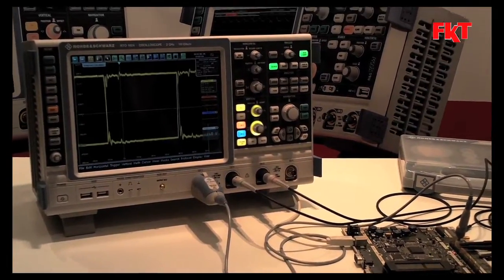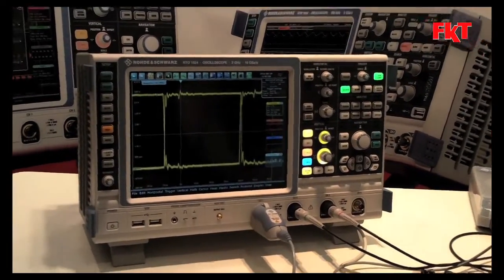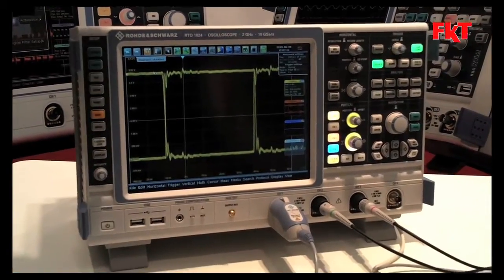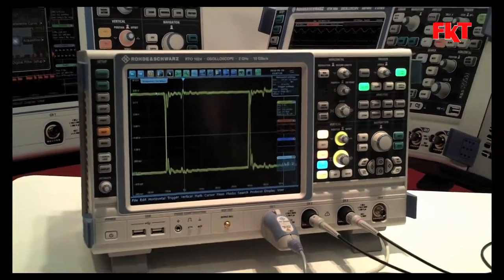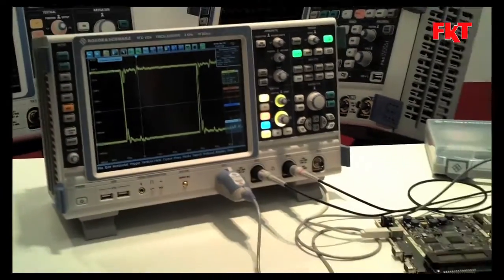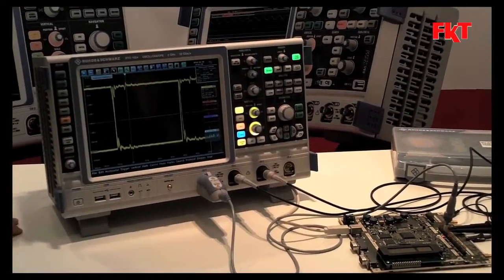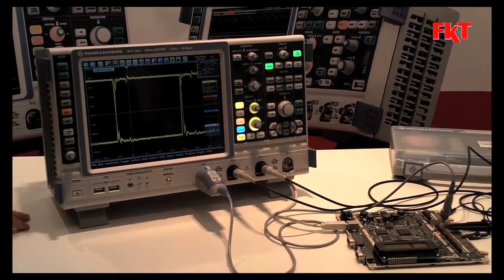I wouldn't use it to make a real measurement of fast-changing DC because it's only for checking the supply voltage. It's a nice tool which complements the portfolio and the function of the probe. But if you expect fast changes, then of course it's even better to have a look at the oscilloscope, because that's not the main target of this DC measurement.